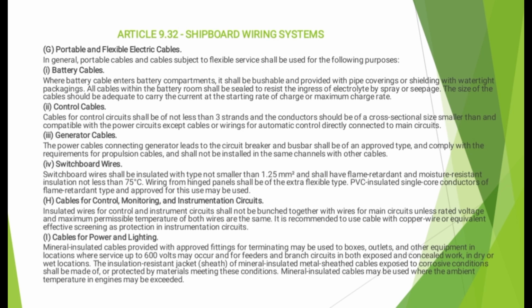Control cable should have at least 3 strands and be smaller in cross-section than power circuit, except for automatic control directly connected to main circuits. Generator cables must be of an approved type, comply with propulsion cable requirements, and not be installed in the same channels with other cables. Switchboard wires must have flame retardant and moisture resistant insulation not less than 1.25 mm and be suitable for temperatures up to 75 Celsius.